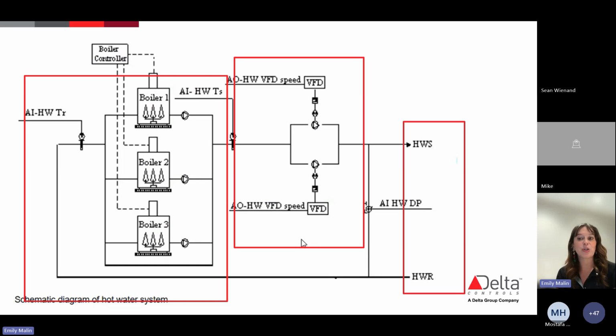The important part about this too is that once that room is warm enough, once we hit that set point, we need to build something into our controller, our program, and our sequence of operations that then tells that valve to close, so that we're not heating up our guests and doing things that are just going to waste all of that energy. The final piece of this is in the bottom right-hand corner, our hot water return. That's what is returning back to the boiler after the water has released all of its heat. It's already cooled down, it flows back into the boiler, and then the system just loops and happens again.